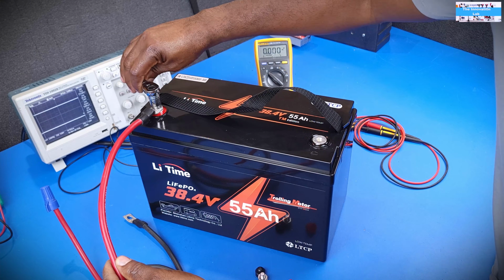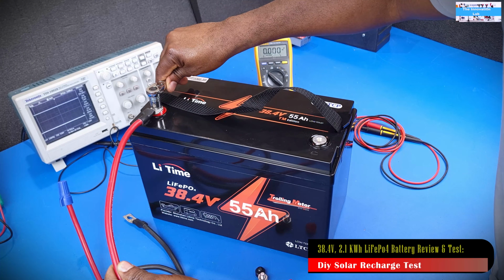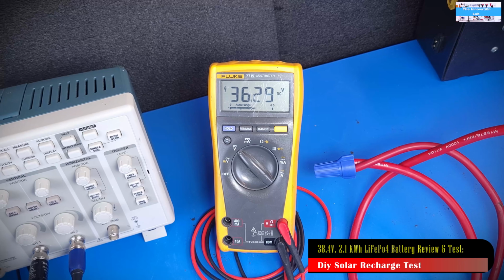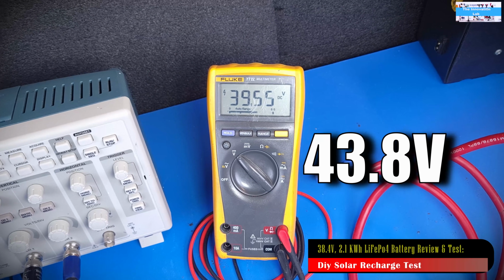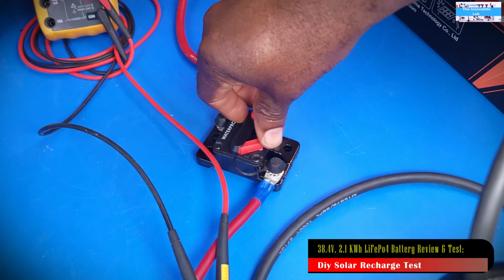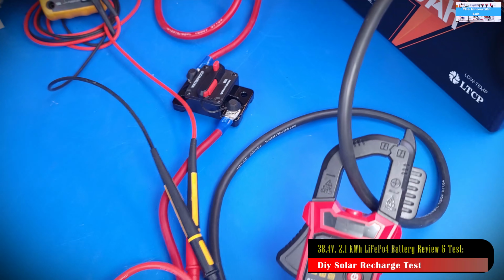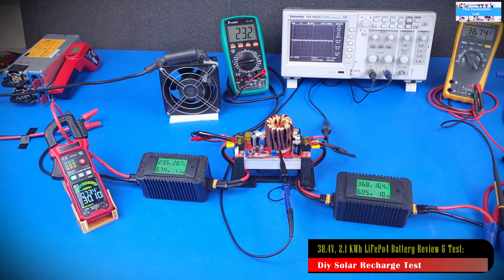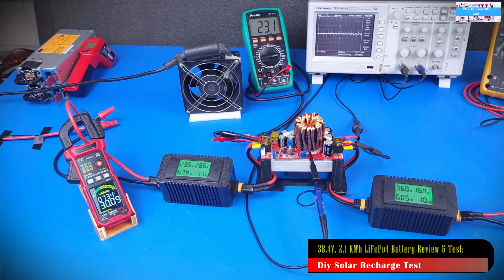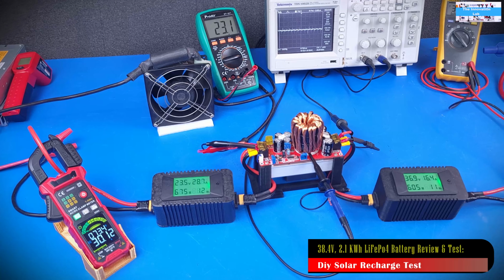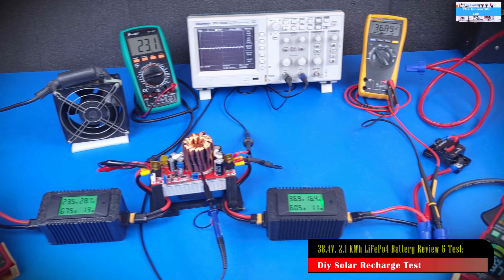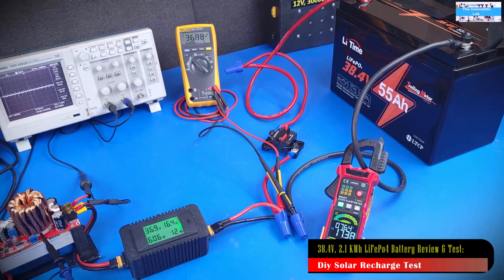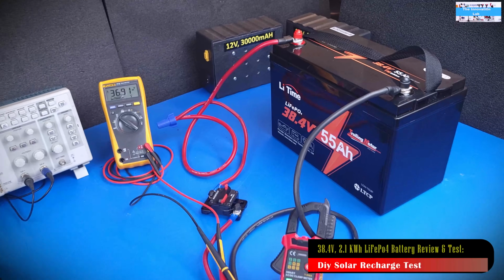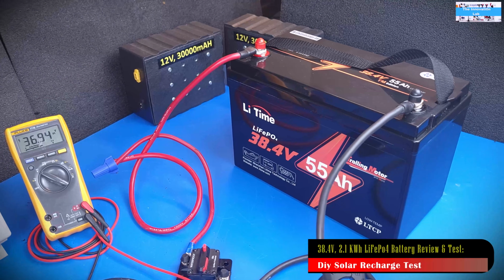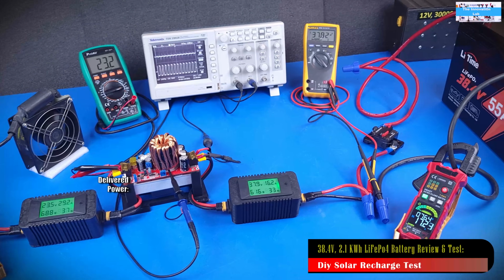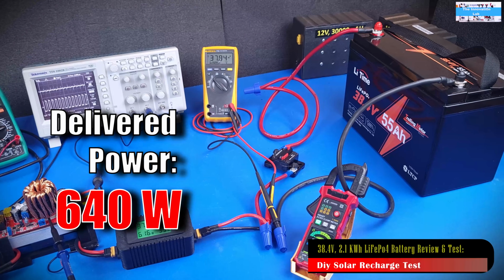All we had to do was connect the battery to the DC to DC boost converter. We adjusted the output voltage to match the manufacturer recommended charging voltage, about 43.8 volts, then closed the circuit breaker and slowly increased the charging current. Overall, with the battery connected, the solar panel system was delivering about 30 amps to the charging system, and the battery was receiving a charging current of about 17.38 amps during the constant current phase. Considering the charging voltage and current at the time, we saw a continuous delivered power to the battery of about 640 watts during constant current mode.